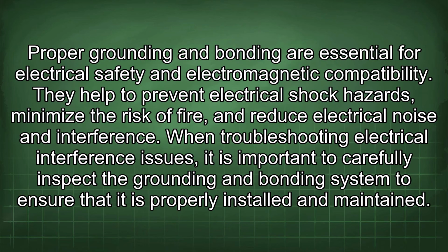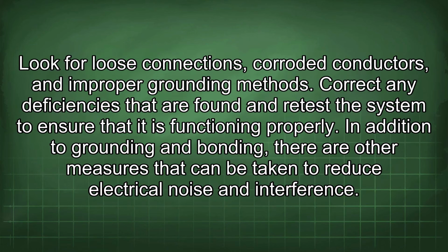Proper grounding and bonding are essential for electrical safety and electromagnetic compatibility. They help to prevent electrical shock hazards, minimize the risk of fire, and reduce electrical noise and interference. When troubleshooting electrical interference issues, it is important to carefully inspect the grounding and bonding system to ensure that it is properly installed and maintained. Look for loose connections, corroded conductors, and improper grounding methods. Correct any deficiencies that are found and retest the system to ensure that it is functioning properly.